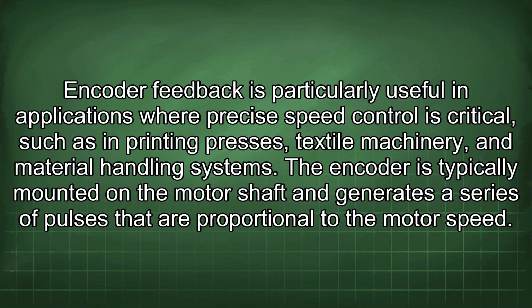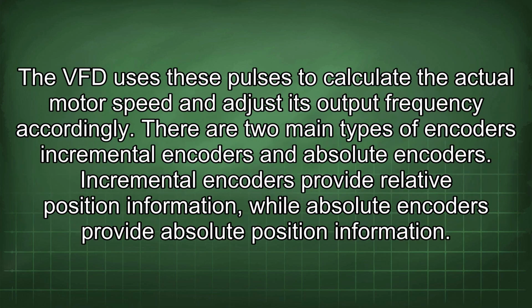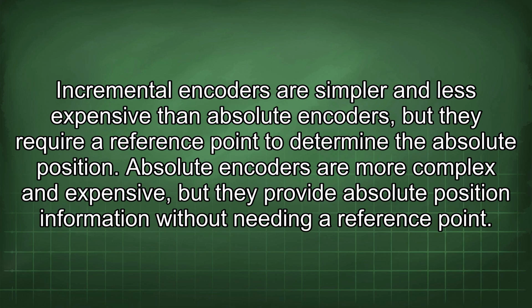are proportional to the motor speed. The VFD uses these pulses to calculate the actual motor speed and adjust its output frequency accordingly. There are two main types of encoders: incremental encoders and absolute encoders. Incremental encoders provide relative position information, while absolute encoders provide absolute position information. Incremental encoders are simpler and less expensive than absolute encoders, but they require a reference point to determine the absolute position.